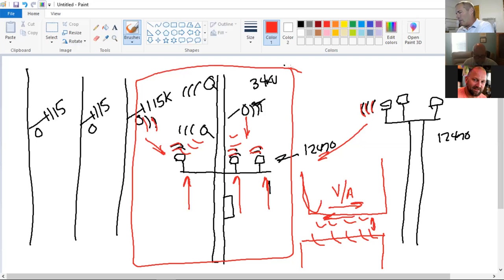I've got a high voltage on top, and now I'll have a lower voltage, though still substantial, on the bottom. That's what was happening with that guy in the bucket truck—he was grounding this line or something similar. Everything around him was de-energized. He was grounding the line and actually picking up voltage. Where was that voltage coming from? The other lines—magnetic induction.